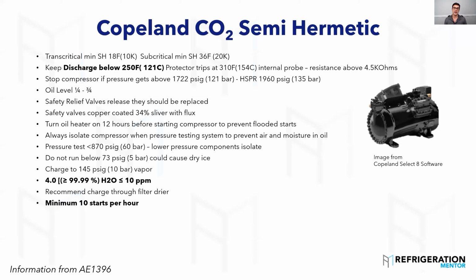Here's another difference. So anything that I bolded was different than the Bitzer one. So minimum 10 starts per hour. Or Bitzer said 6 starts per hour. Copeland says minimum 10 starts per hour. And all this information that you want to get is from down below. There's AE1396. And I'm going to show you how to get to these bulletins. So when you're working on them, you can find them fast. So 10 starts per hour.